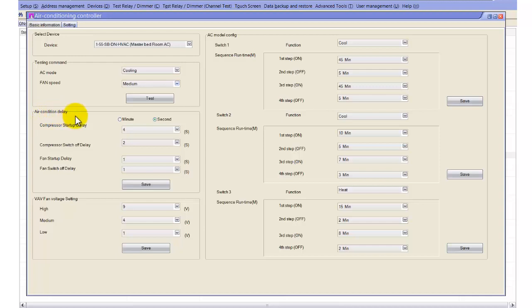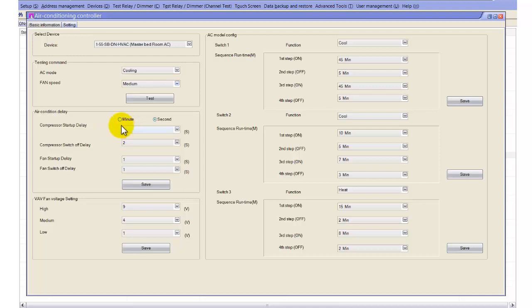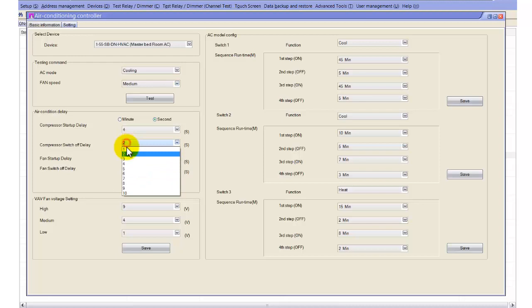Here you can see the air conditioning delay. We use this delay for startup and also the compressor switch-off delay. When someone switches on the DLP, it takes 4 seconds to run — this is for protection, because switching on and off quickly may damage your compressor. When you press on and off, nothing happens immediately; after 4 seconds the AC turns on. When you turn off, it also takes 2 seconds to switch off, so the compressor is not affected by rapid on/off commands. We always keep it at 3 or 4 seconds.